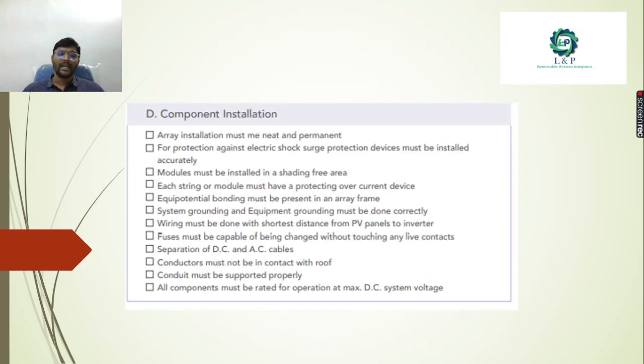And even component installation is very much important. Make sure PV array modules have been installed and it is neat and clean. Make sure inverters are installed at safe locations. Make sure wiring has been routed properly, and the grounding has been routed properly. There should be a separation between the DC cables as well as the AC cables.